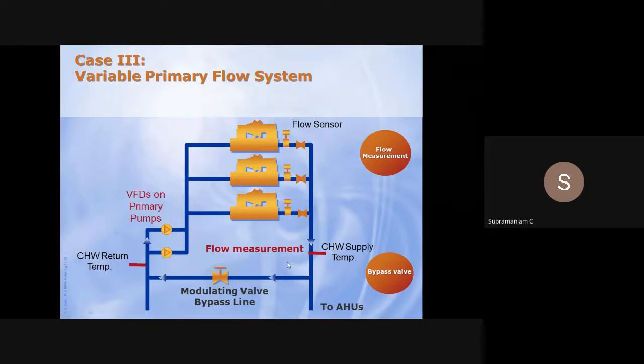Variable primary flow is the same thing as before, but you will not find the secondary pump, because the VFDs have shifted from the secondary pump to the primary pump. And what is the other thing we find here? Flows. The measurement is very important in variable primary flow. What are the advantages of variable primary flow? Your number of pumps are fewer, your electricals will be less, and your only concern is that your control logic has to be very good.